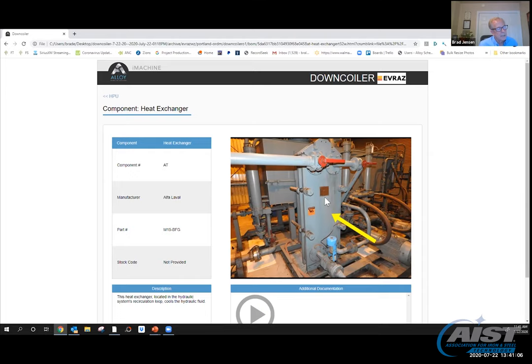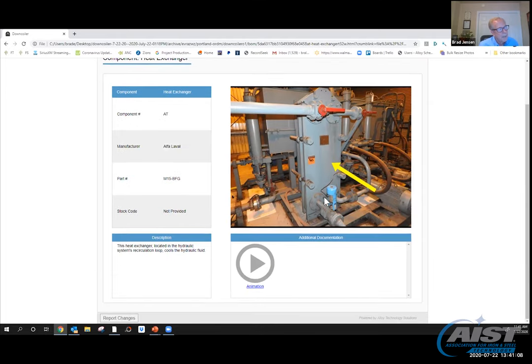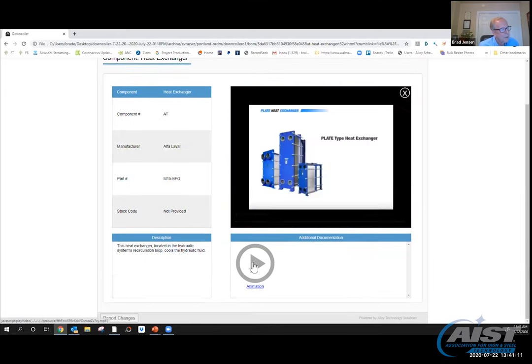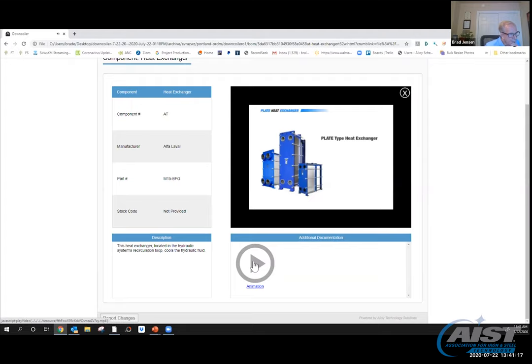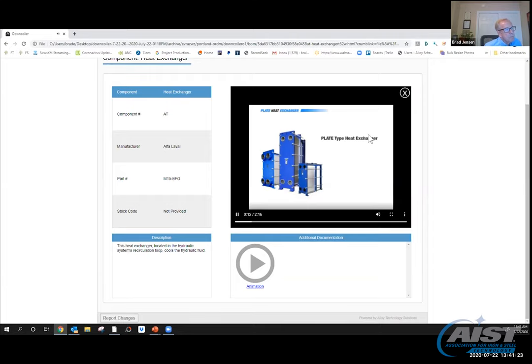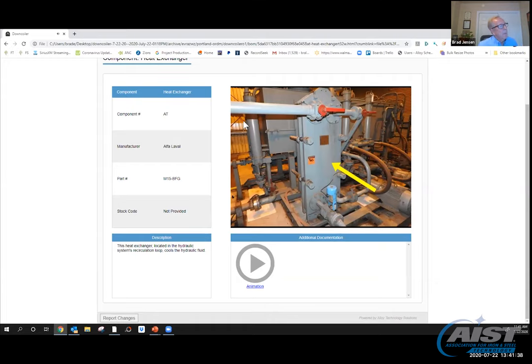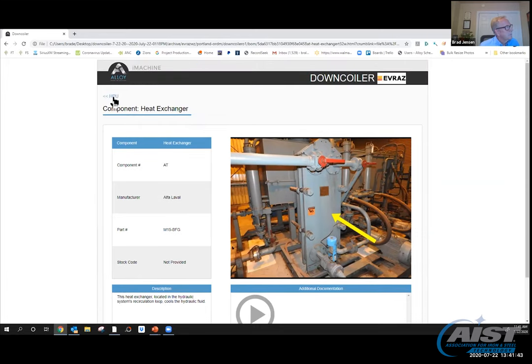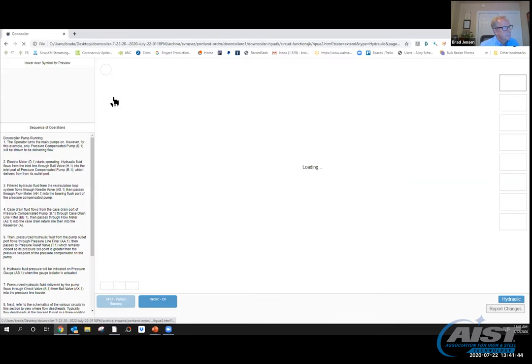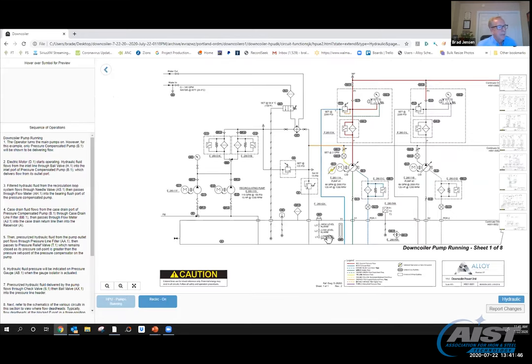The arrows, instead of pointing in as shown down here, they're pointing out. I'm taking the warmer fluid on the heat exchanger and removing it back out through this cool water circulation here. You can see on the picture on the left, this is what I'm actually referring to. That could have been a tube and shell—this is a plate heat exchanger, but the symbol is the same. The symbol indicates what it does, not what it looks like. Always remember that. A plate heat exchanger is a specialized design well suited to transferring heat between medium and low pressure fluids. This type of heat exchanger is used extensively throughout the industry, particularly in applications that require a large amount of fluid heat to be removed in a relatively short period of time.